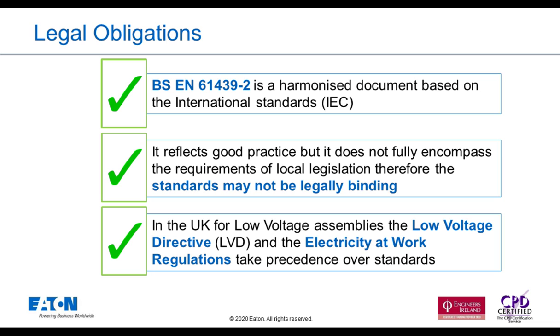So a little bit on the legal side. Most national standards are a harmonised document based on an international standard, and 61439 is no exception. Although it reflects good practice, it doesn't encompass the local legislations. Therefore, the standard is not legally binding. Specifically in the UK, we have the Low Voltage Directive and the Electricity at Work Regulations. These take precedence over the standard. Similarly, if you're joining us today from another country, you'll have your own laws and regulations in your country, and the same rules apply.